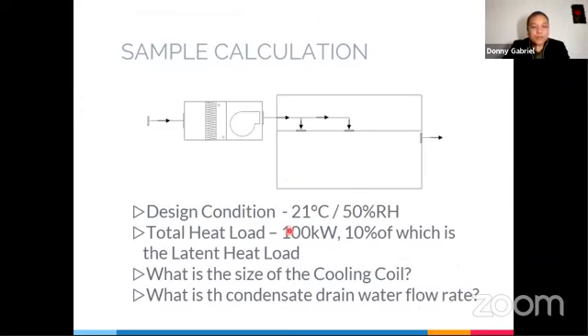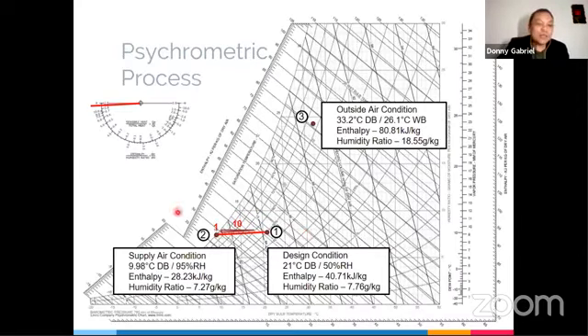Going back to our condition. The total heat load is 100 kilowatt. It says here 10% is latent heat load, which means sensible heat load is 90 kilowatt, and 10 kilowatt is our latent heat load. For those who joined us in our ACMV series, the quotient of the sensible heat load over the total heat load is called the sensible heat ratio. What is sensible heat ratio? The ratio between the sensible heat and the total heat. So by having sensible heat over total heat, we will get a 0.9 or 90% sensible heat ratio.